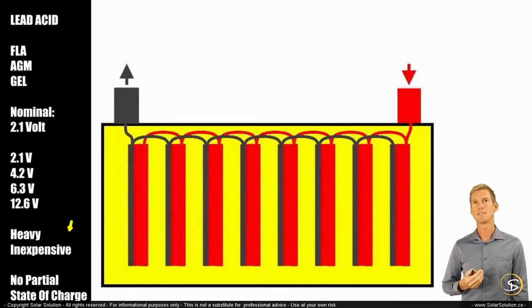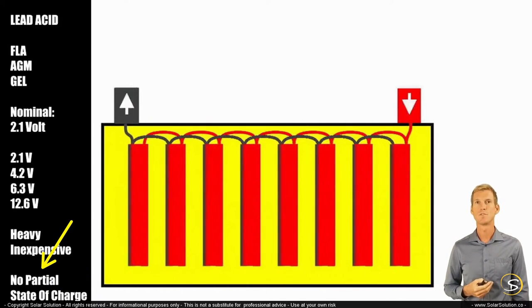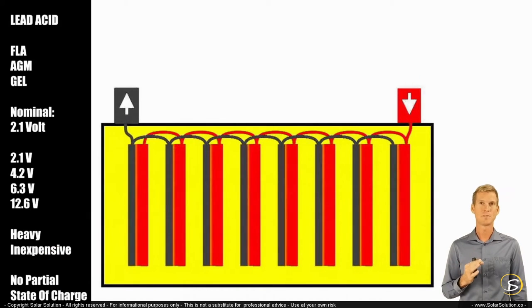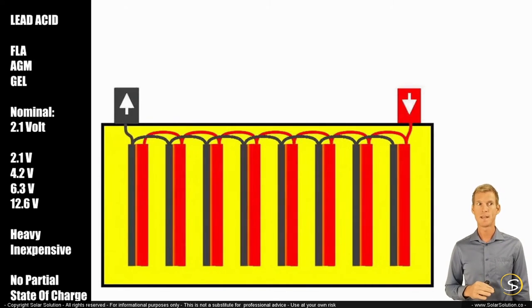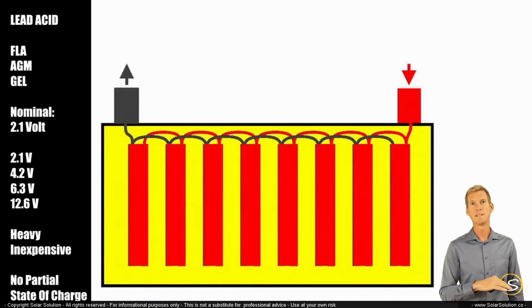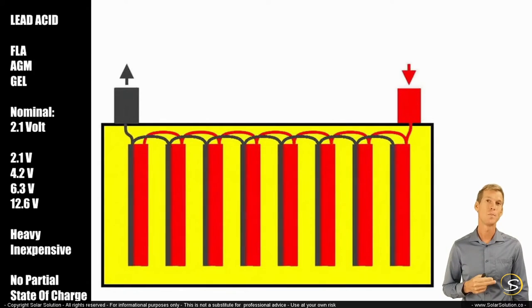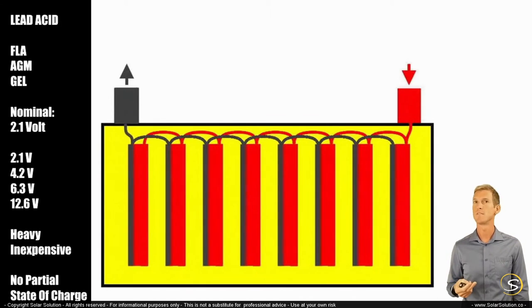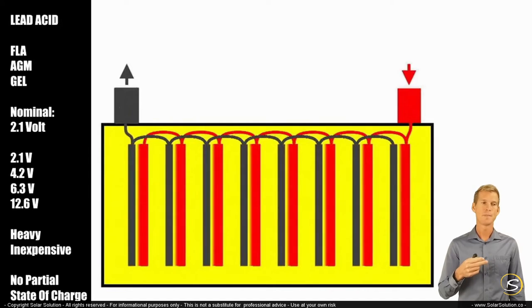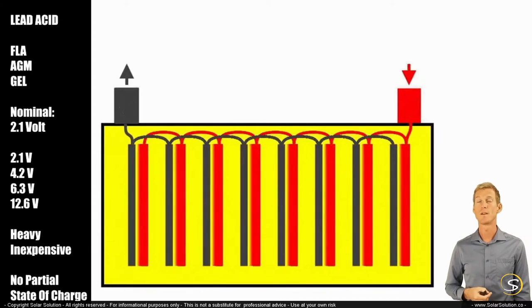A significant disadvantage of lead-acid-based batteries is that they do not allow a partial state of charge over a prolonged amount of time — it can be days or weeks depending on the chemistry. They do not like you to discharge the battery and then let it sit in a partially discharged state. If you leave it for a prolonged time, you cannot fully reverse the electrochemical reaction anymore, which affects the lifetime and capacity of the battery. In general, lead batteries don't like partial state of charge for a prolonged amount of time.